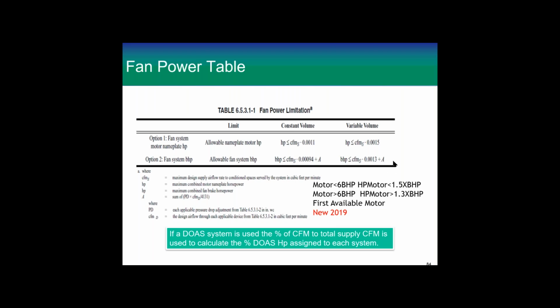So if that passes, your brake horsepower plus the A's plus that, then you can go forward. But you need to be careful because we've had several times when a manufacturer will send us a selection, and normally it's a little bit of the ductwork we've got on it, but there's tremendous internal pressure drop happening inside a lot of the units. We're asking for smaller and smaller boxes with more and more stuff in them, and it's not their fault. We just have a lot of stuff, and we keep wanting to build a smaller room. Anyway, if they send it to you and you design around it, and then you get to the end, now you can check these.